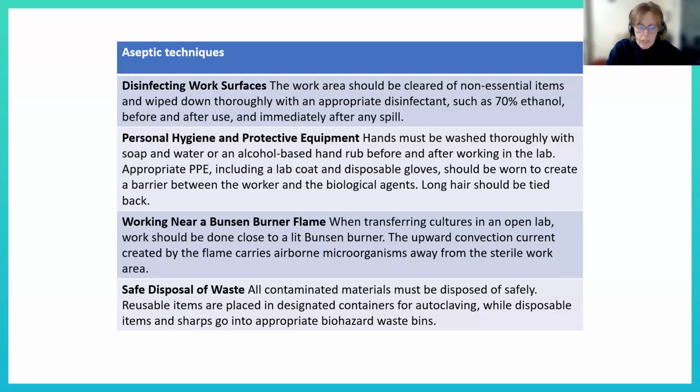Right, all the waste is sorted into different containers, and then it is autoclaved. It goes into a special bin which is taped up, and then it's autoclaved, which means it's exposed to really high temperatures and pressures, essentially like a huge pressure cooker. So really hot and really high pressures, and that will kill anything else off that's managed to get through all these safety loops.